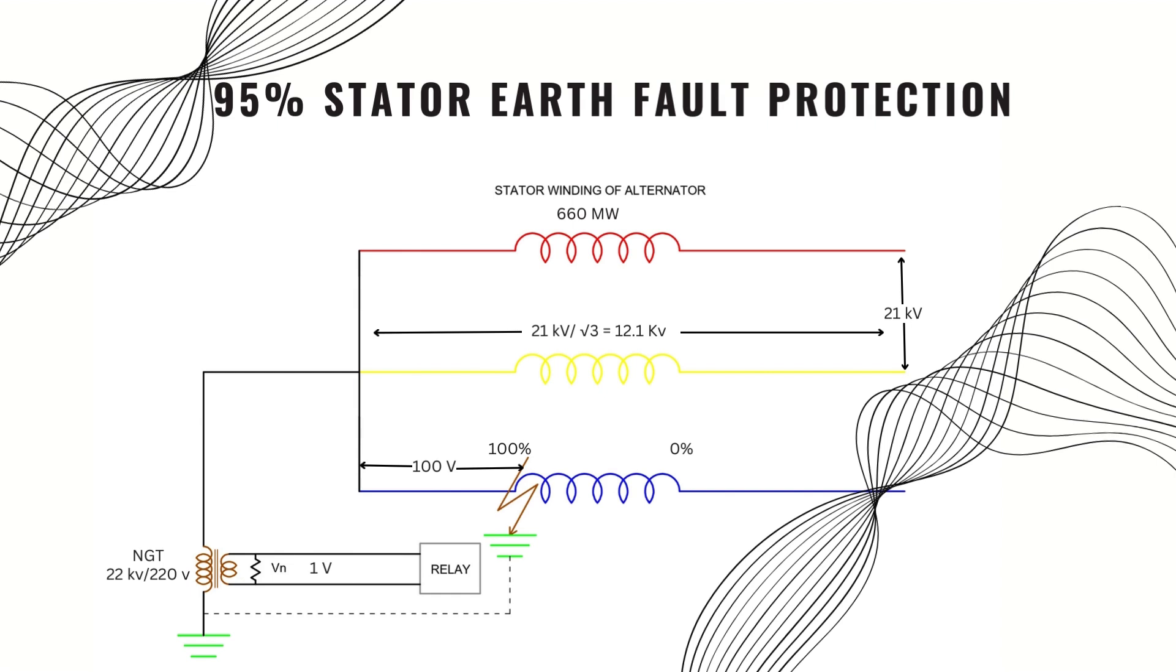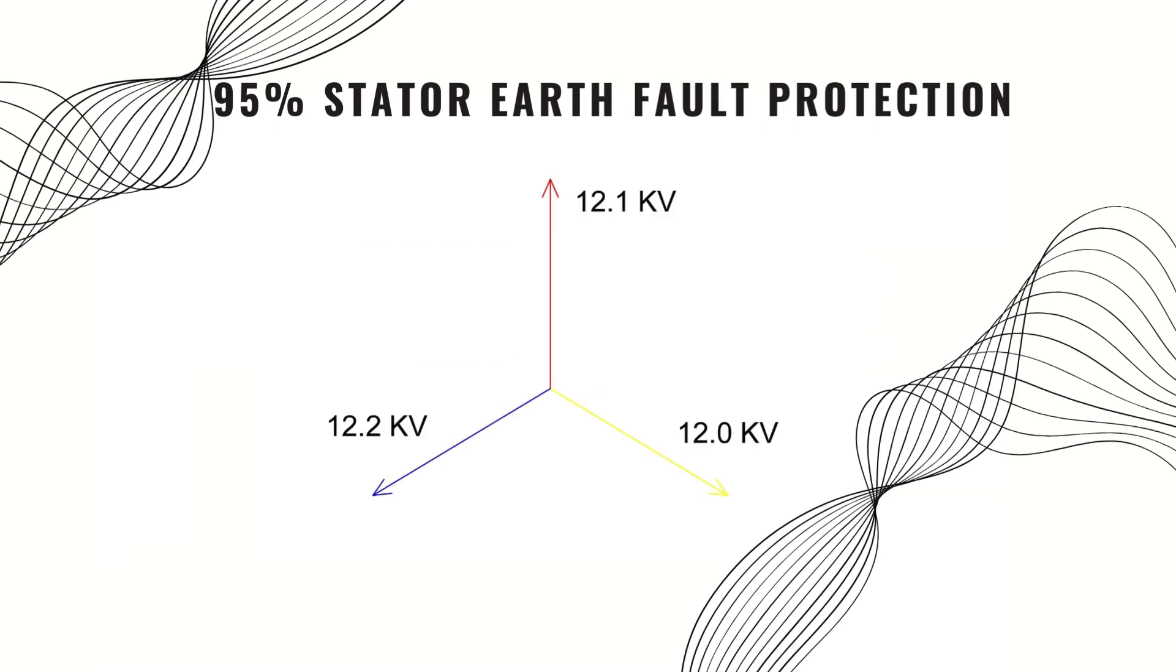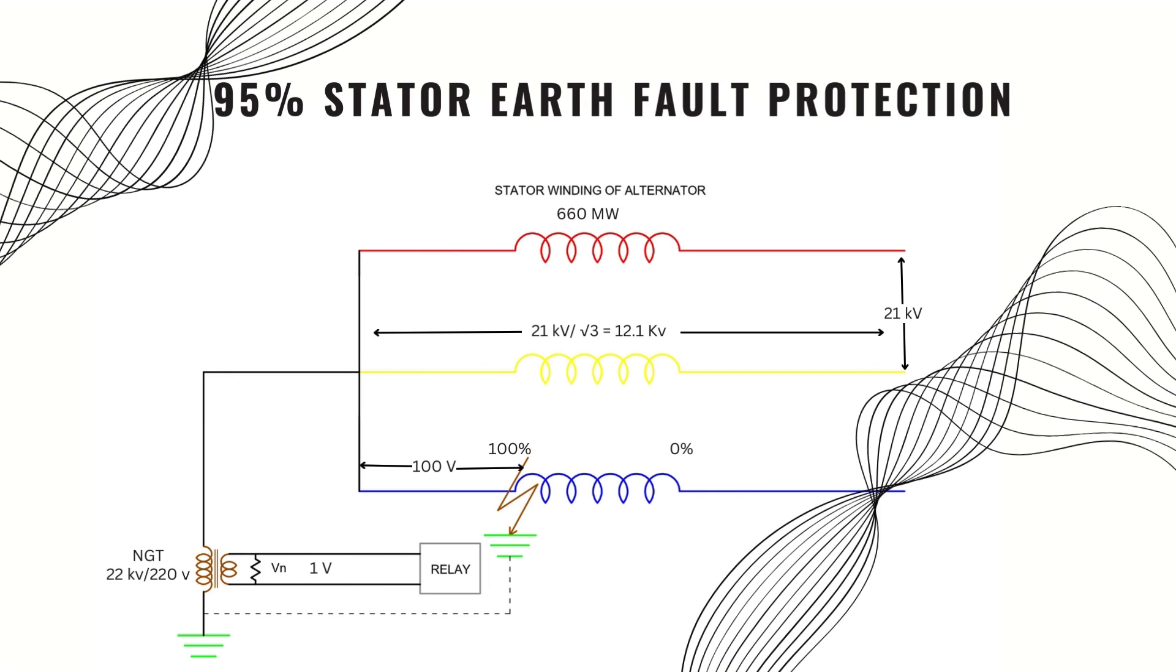Now you may ask, why not we set the relay settings at 0 volts? If we set the settings at 0 volts, then 100% of the winding will be secured. But there is a problem we have discussed earlier that the terminal voltages are not exactly the same. There must be some small unbalance that reflects on the neutral point and for that reason, VN have some small value of voltage which may create a false tripping. And that is why we protect only 95% of the winding in this scheme.